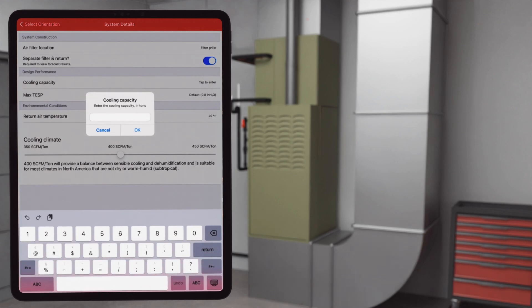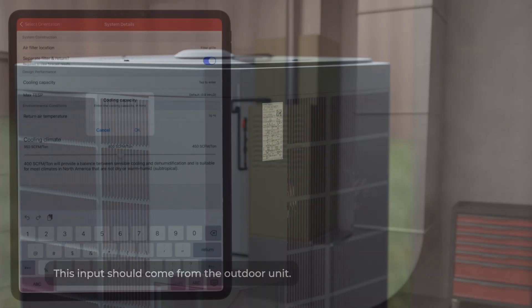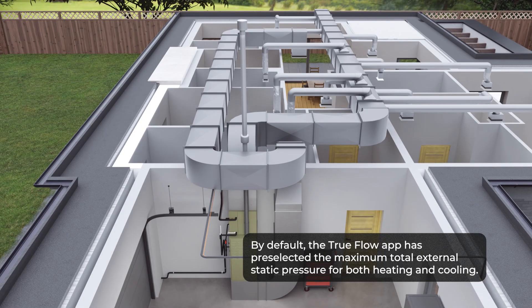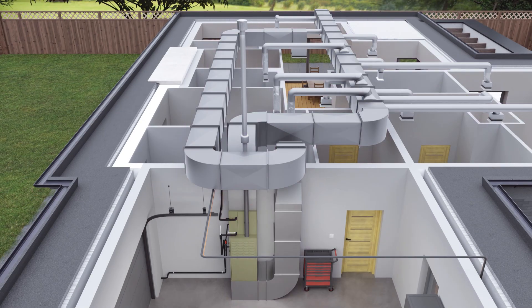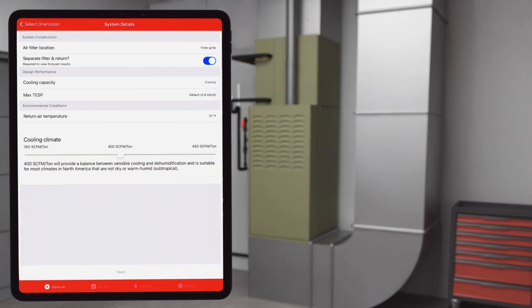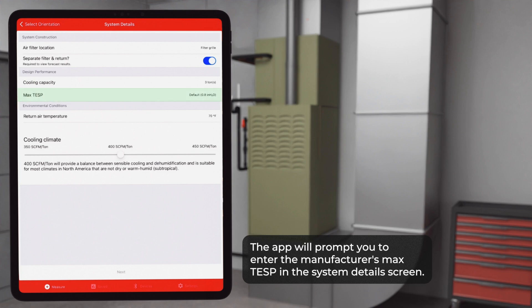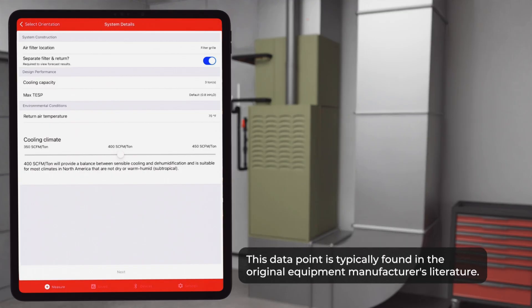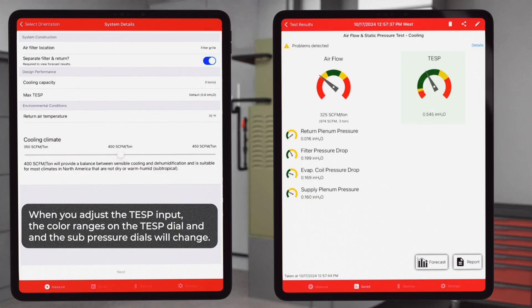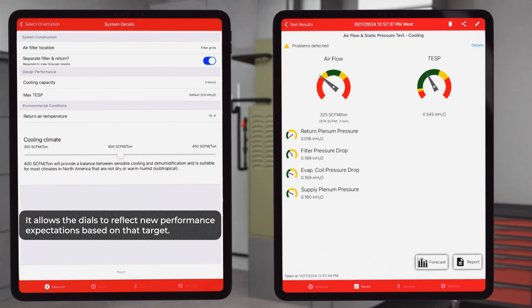Next is the cooling capacity. This input should come from the outdoor unit. By default, the True Flow app has pre-selected the maximum total external static pressure for both heating and cooling. For advanced users, it's recommended to toggle on the manufacturer's max TESP in the app workflow settings. The app will prompt you to enter the manufacturer's max TESP, or total external static pressure, in the system details screen. This data point is typically found in the original equipment manufacturer's literature. When you adjust the TESP input, the color ranges on the TESP dial and the sub-pressure dials will change, allowing the dials to reflect new performance expectations based on that target.